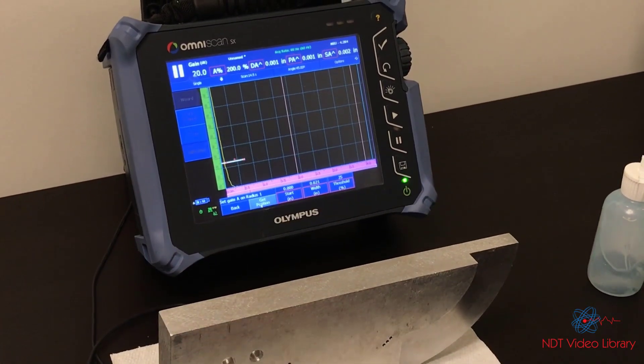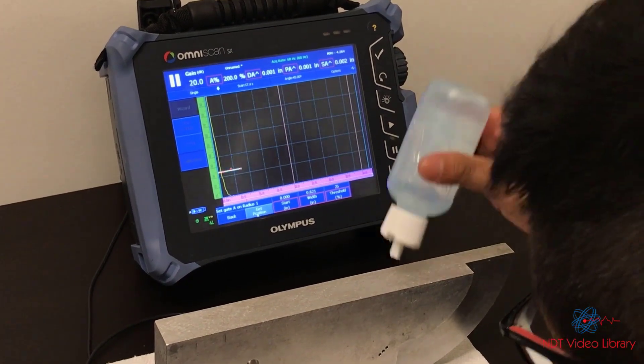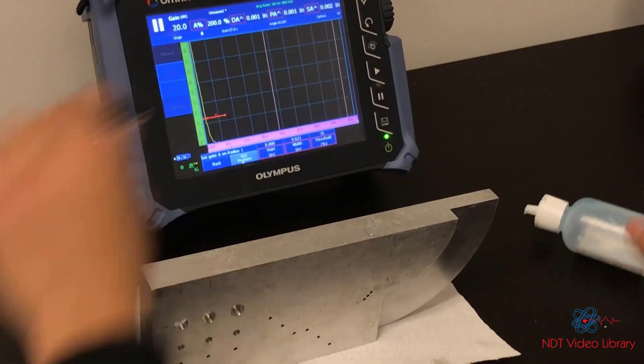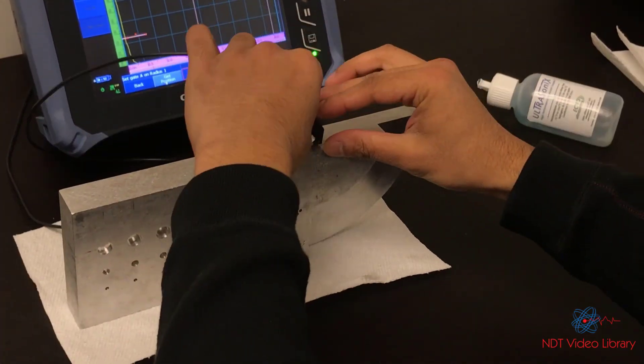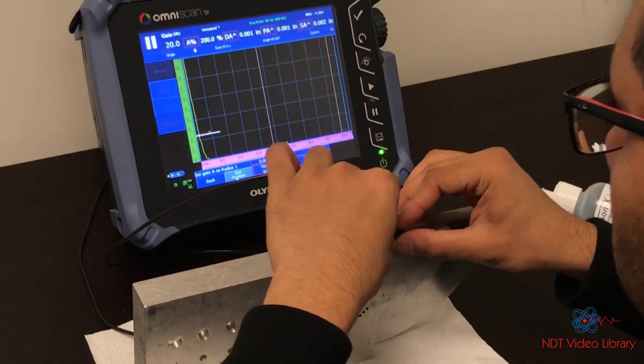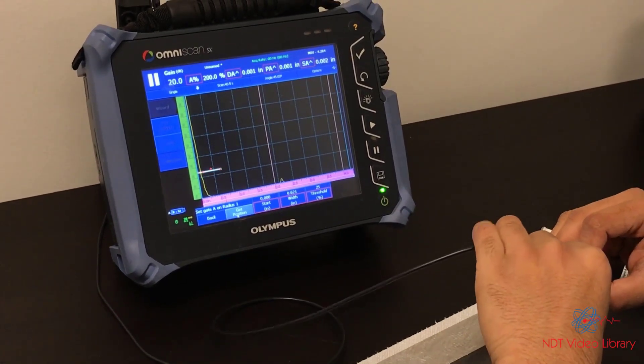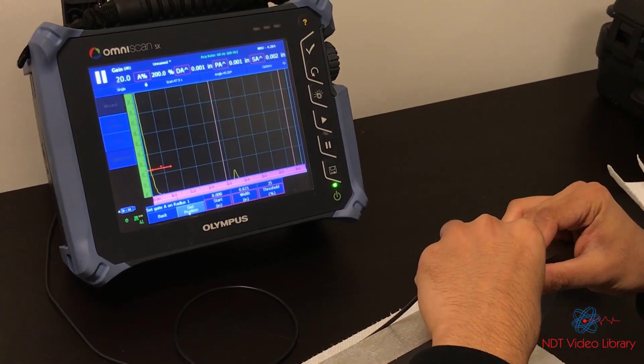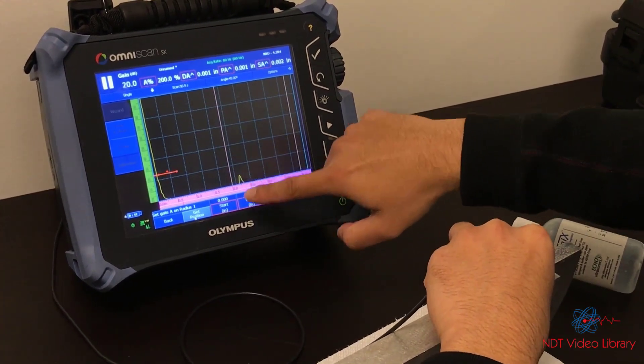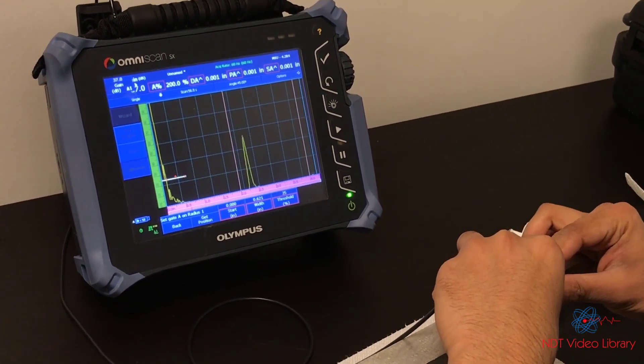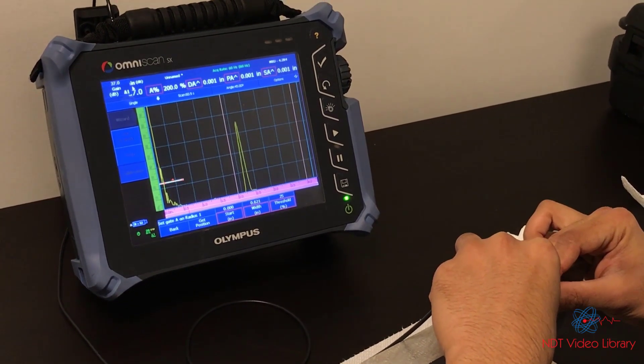Set gate A on radius 1. I need to get the signal for radius 1. I'm going to place my transducer right somewhere about this line because that's kind of the center for this radius. I place it there, try to get a signal, and move it back and forward till it maximizes. You can see that little signal right there. I need to bring it to 80%, so increase the gain.